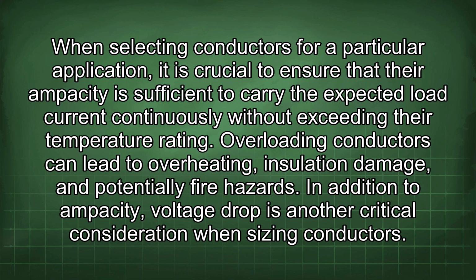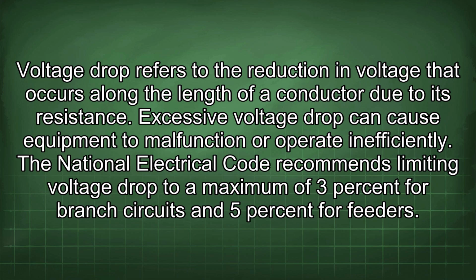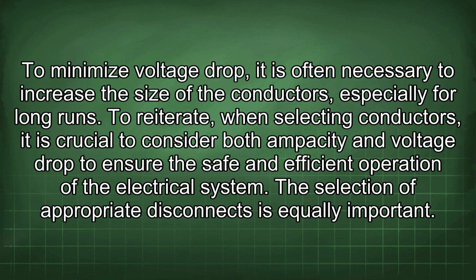When selecting conductors for a particular application, it is crucial to ensure that their ampacity is sufficient to carry the expected load current continuously without exceeding their temperature rating. Overloading conductors can lead to overheating, insulation damage, and potentially fire hazards. In addition to ampacity, voltage drop is another critical consideration when sizing conductors. Voltage drop refers to the reduction in voltage that occurs along the length of a conductor due to its resistance. Excessive voltage drop can cause equipment to malfunction or operate inefficiently. The National Electrical Code recommends limiting voltage drop to a maximum of 3% for branch circuits and 5% for feeders. To minimize voltage drop, it is often necessary to increase the size of the conductors, especially for long runs. To reiterate, when selecting conductors, it is crucial to consider both ampacity and voltage drop to ensure the safe and efficient operation of the electrical system.